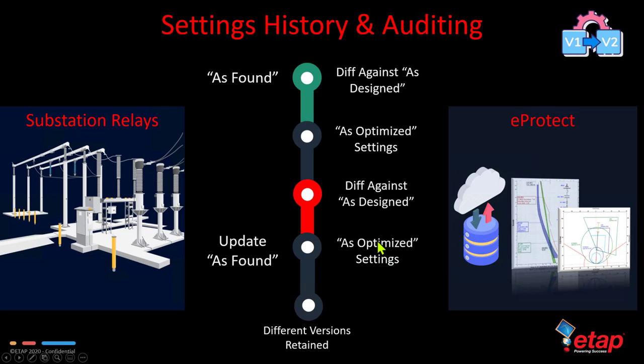So this as optimized setting file can then be updated into the actual relay, and this is essentially known as the updated as found or the new version of the as found. And this is another version that can be differentiated against the previous or the historical as found setting. So essentially different versions are retained on the ETAP software analysis side as well as the eProtect database, and they can essentially be compared at any point with respect to each other. So let's take a look at setting history and auditing in action.